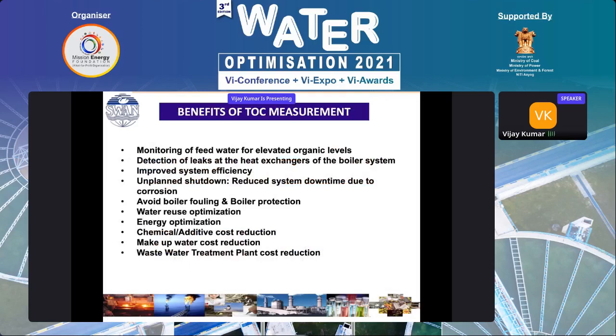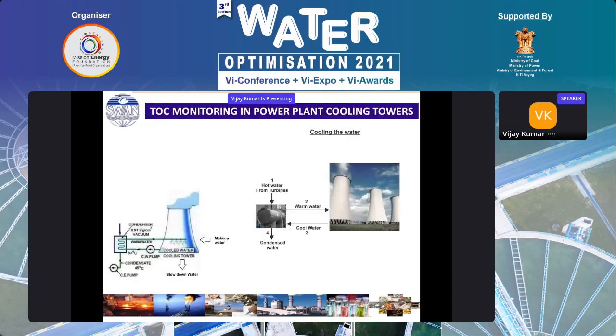By monitoring TOC in feed water, when you see elevated organic levels, it is very important to know why they are coming. It may be due to leaks in the heat exchanger or improved system efficiency. By monitoring, you can reduce the chance of downtime due to corrosion, avoid boiler fouling, and gain boiler protection, water use optimization, energy optimization, chemical additive cost reduction, makeup water cost reduction, and wastewater plant cost reduction. Everything boils down to that.